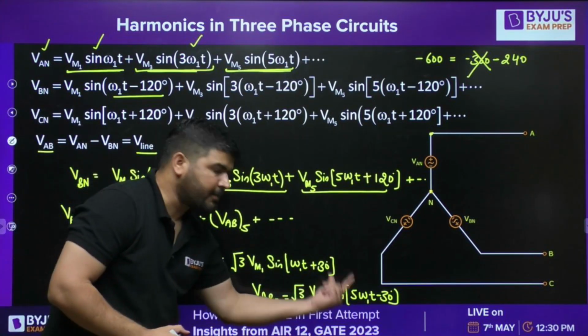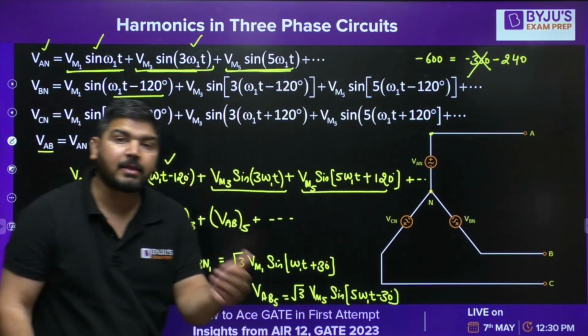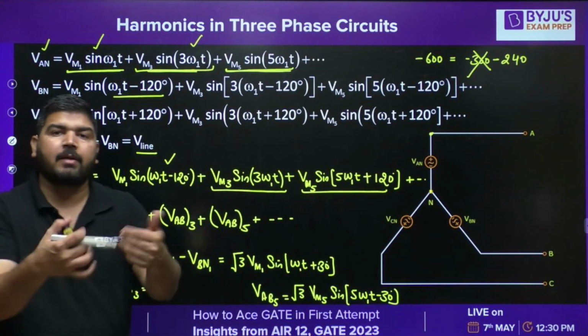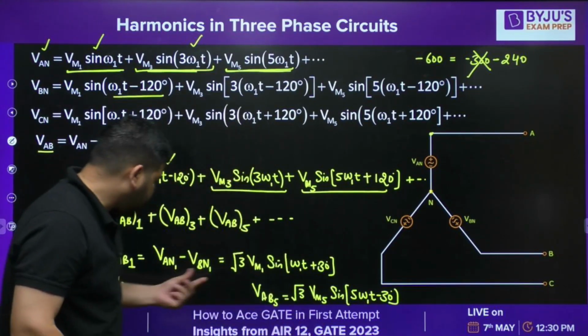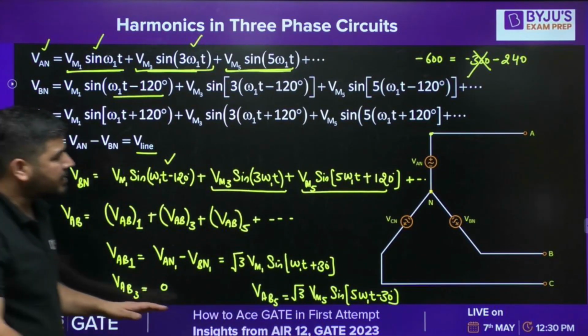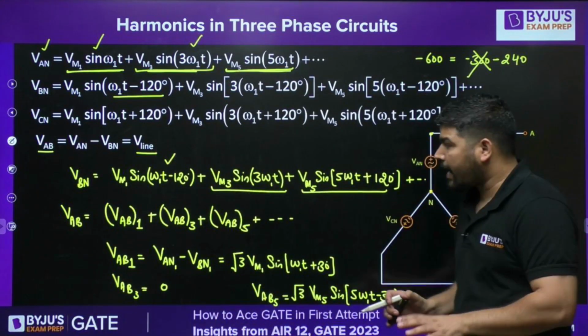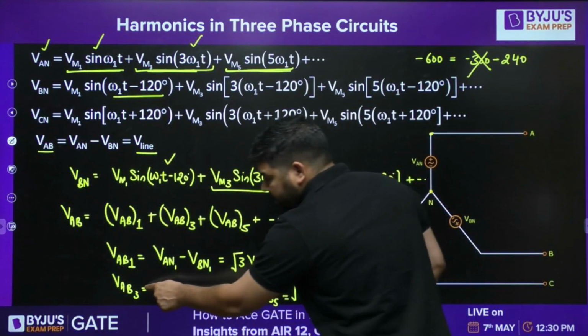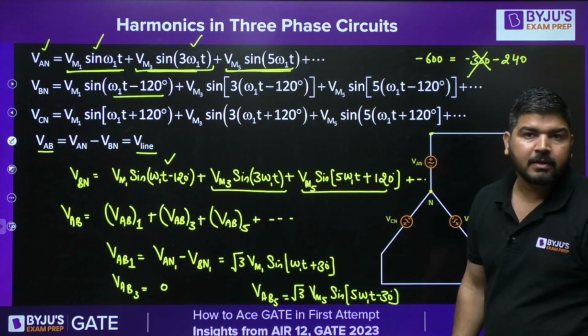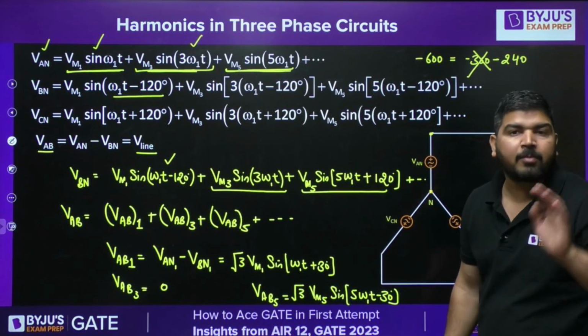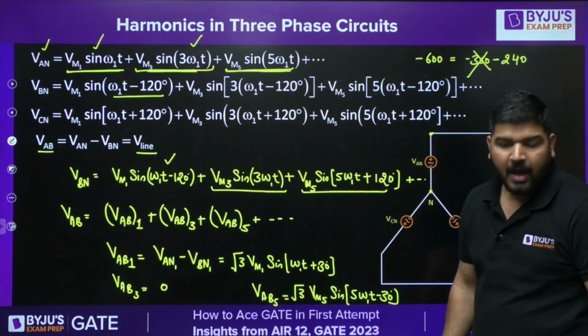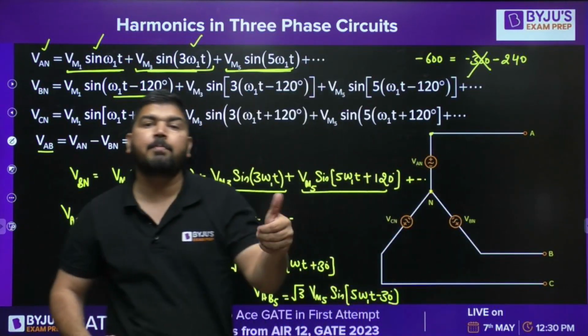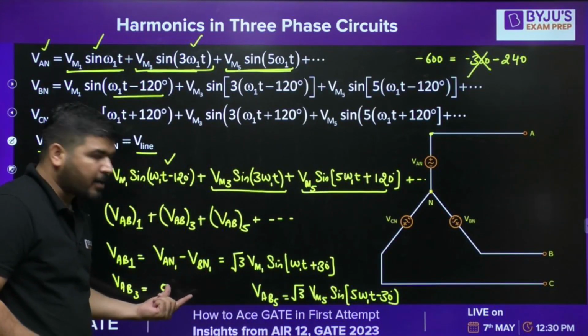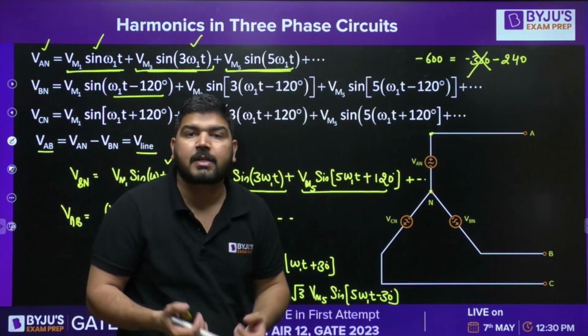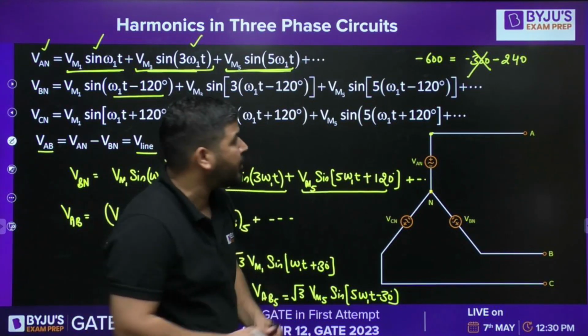Similarly, you can calculate the seventh harmonic and then the ninth harmonic. The ninth harmonic will again be zero. It means in the line voltage, the harmonics which are odd multiples of 3 will be absent. Odd multiples of 3 are known as triplen harmonics. Now what are those harmonics?